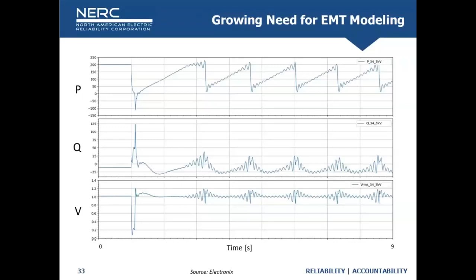But we're seeing a lot of modeling challenges all around. A good example there at the top: two models, one RMS positive sequence simulation, one EMT simulation, exact model, detailed representation, supposed to be exactly the same representation in two different software tools, and it was simply a parameterization error. Somewhere in that code, there was a per unit value that was set on the wrong base, and you get a vastly different response. Not much you can do from a planning aspect, but it shows the need to have that benchmarking.